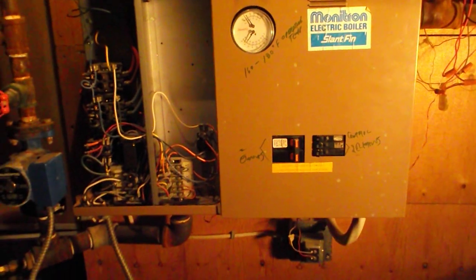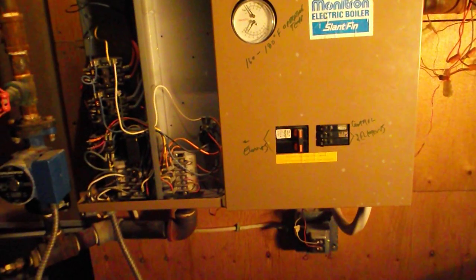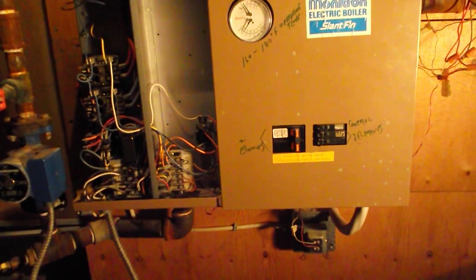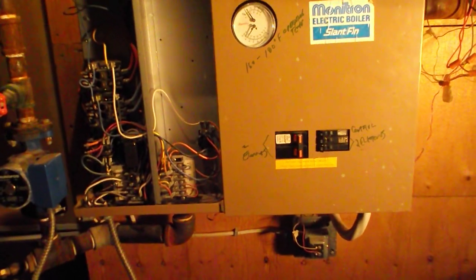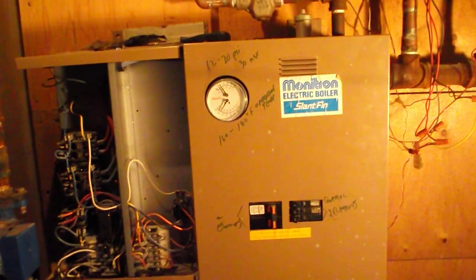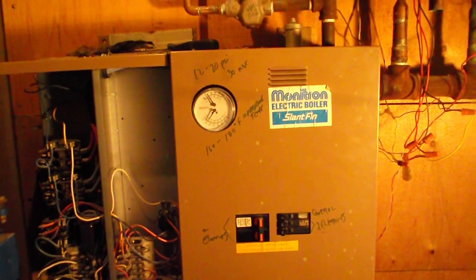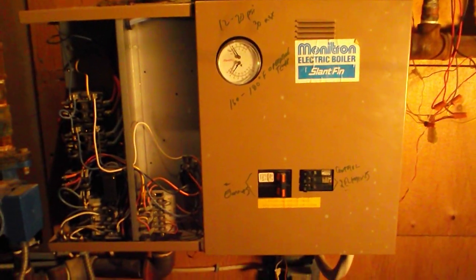The problem that initially led to the investigation was just a no-heat situation. Turn the thermostat on and no heat would come out of the registers, but through the troubleshooting process we learned a bit about how these hot water baseboard boilers work, so I'll cover them from start to finish.